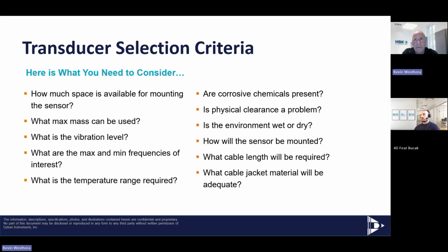The next thing that we talk about is the vibration level. What is the energy we're going to be measuring? What G range do we need to measure? If you don't know, you can share some rough details of the application, and either myself or our engineering team can determine roughly what the appropriate G level would be for your application. Then we need to talk about frequency, both minimum and maximum - what's the lower end frequency you need to measure and the upper level frequency that needs to be measured. Then we get into the environment.